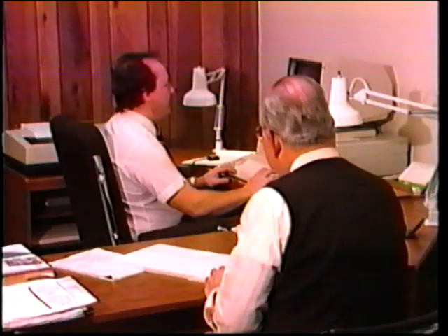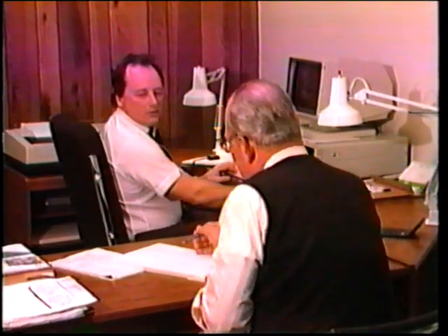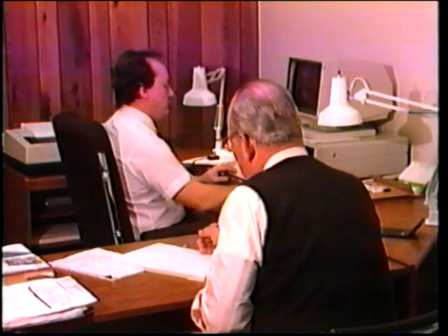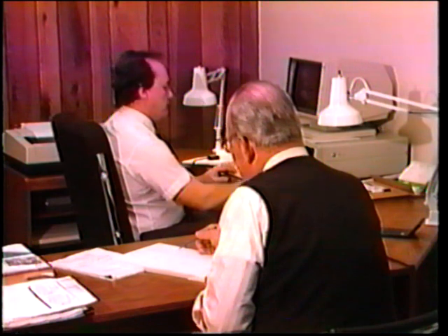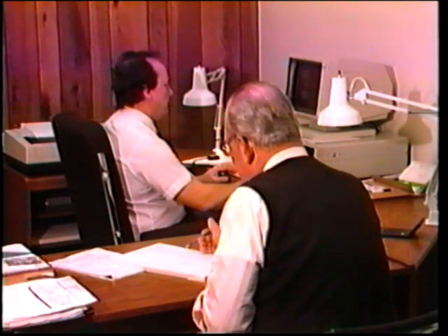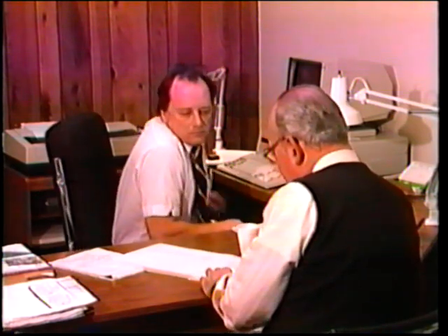One of the relay technician's main tasks is to check and calibrate relays and adjust the settings according to predetermined calculations. In many utility companies, these calculations are performed by a specialist group aided by computer programs. We feel that the relay technician should be aware of how these calculations are performed, along with other factors which must be considered in determining relay settings.